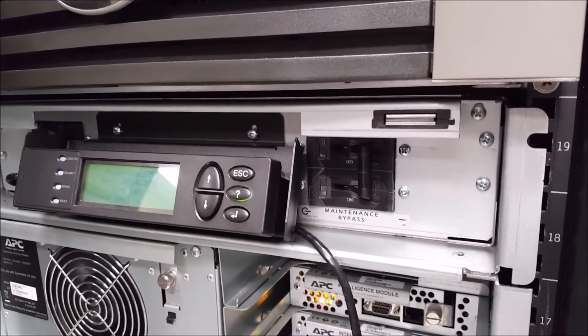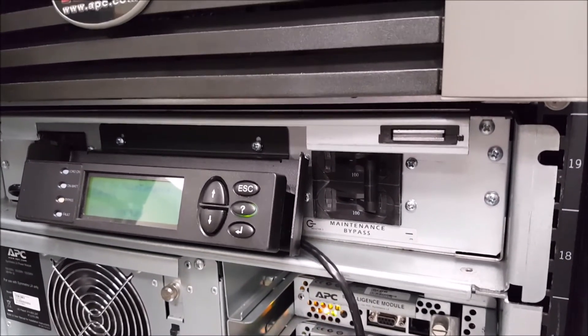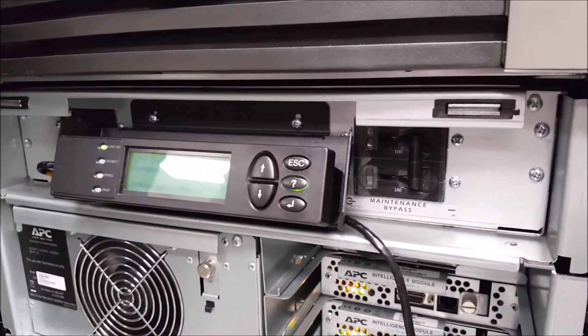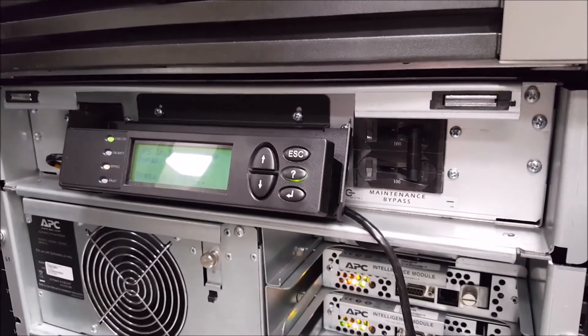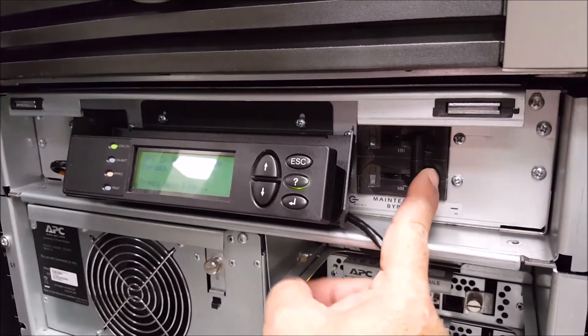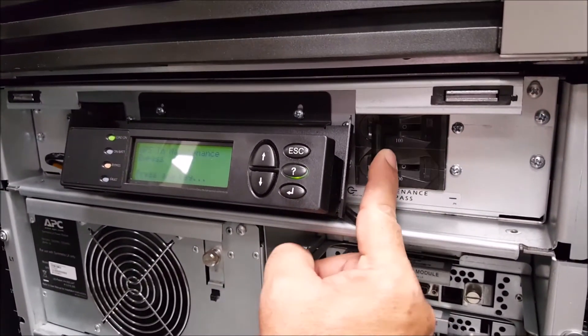Once you've verified that everything seems to be working normally, you'll take the UPS out of maintenance bypass by flipping the maintenance bypass switch from the right back over to the left.